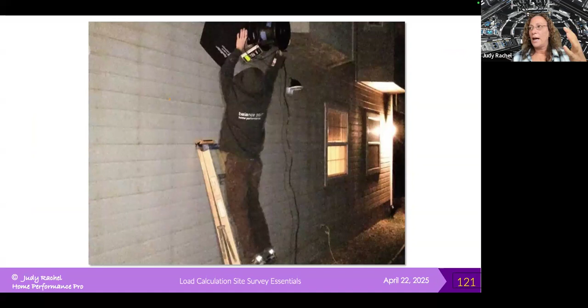So, concluding comments. Really, the load calculation is a balancing act. Producing an accurate load calculation is a balance between what we can accurately describe about the building assembly and making informed, aggressive, best assumptions regarding the details of the building assembly that we're unable to precisely determine. So when we can do things such as the duct leakage test, or when we can do the blower door test, those types of things are helping us to do a more accurate load calculation.